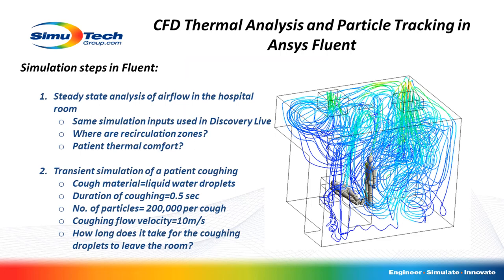After bringing my selected design into Fluent, I start by performing a steady state simulation using the same simulation inputs I used in Discovery Live. I want to gain more insight into the airflow, identify recirculation zones, and evaluate the thermal comfort experienced by the patient. I will also take this demo one step further and show how to perform a transient simulation of the patient coughing — assuming liquid water droplets, a cough duration of 0.5 seconds releasing 200,000 particles, at a flow velocity of 10 meters per second.